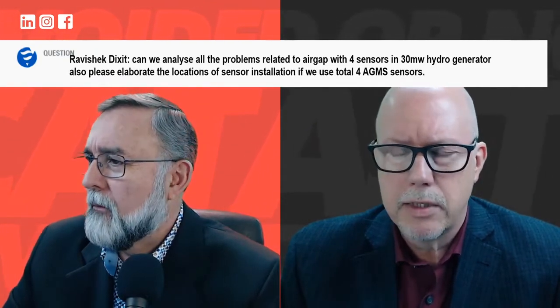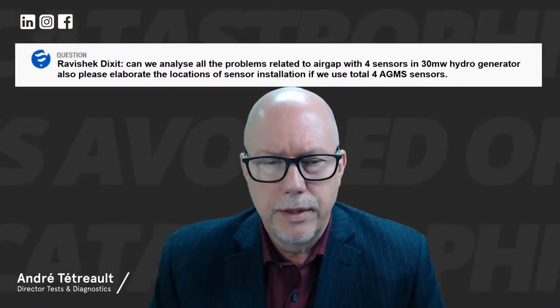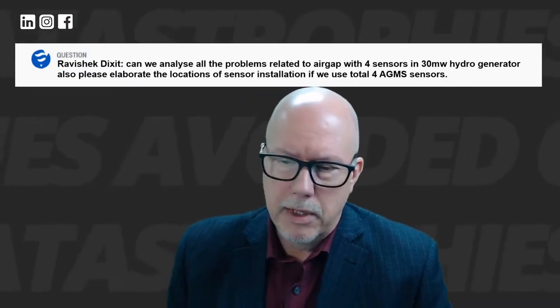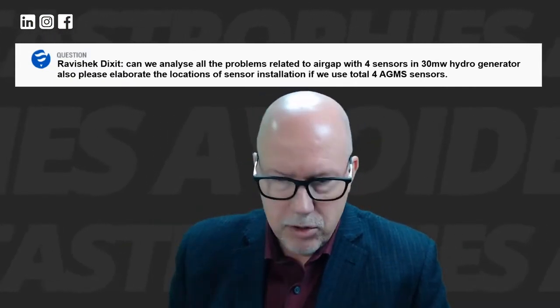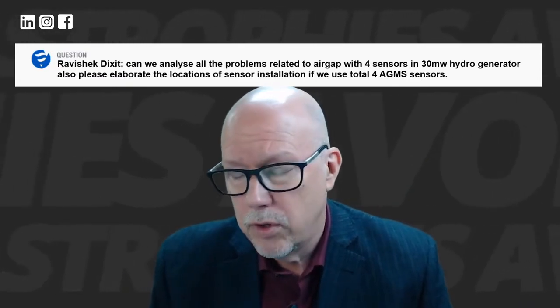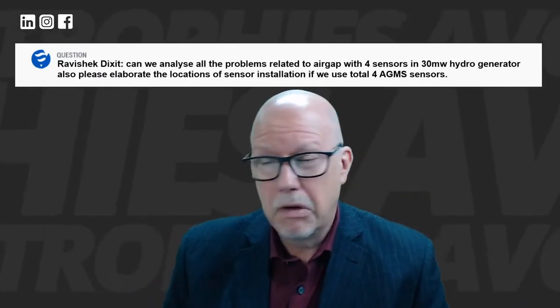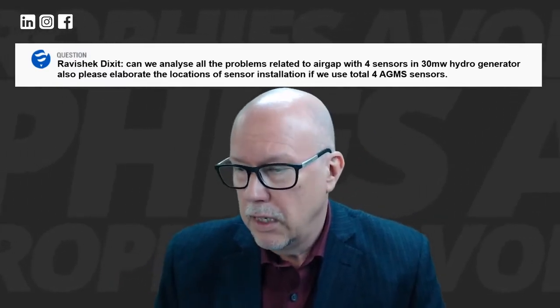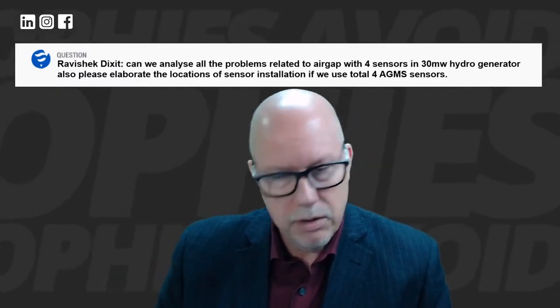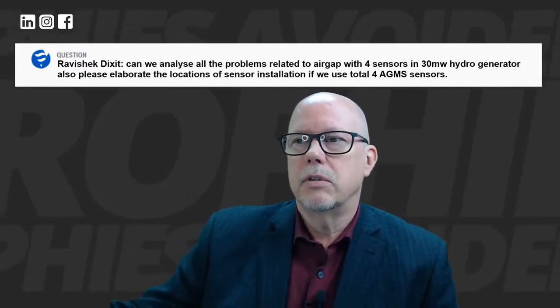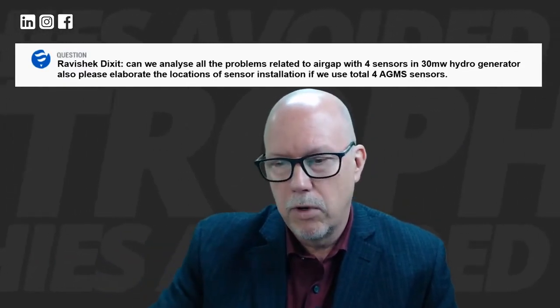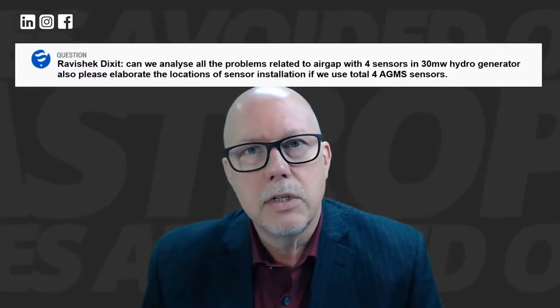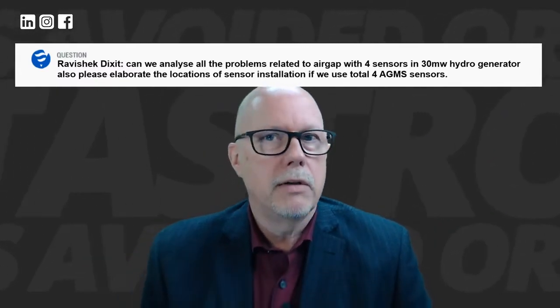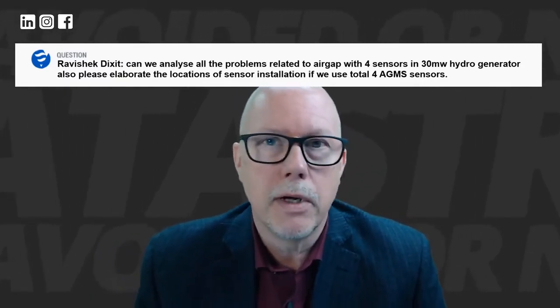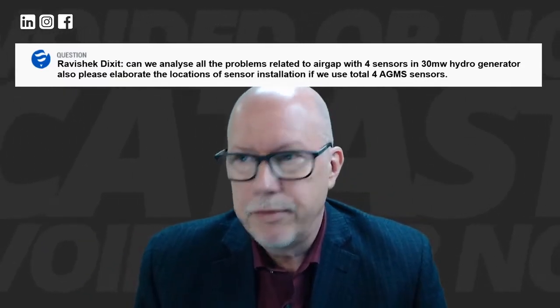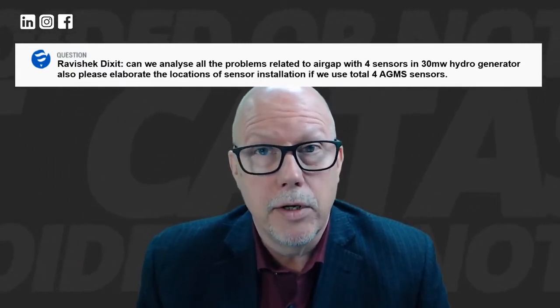I've had many discussions with utilities or OEMs talking about how many sensors, or even if sensors were pertinent, because the unit's very small, we generate only 10 megawatts, and it's not a cost-efficient exercise for us to put this type of equipment with this cost on smaller units. And my response is always, well, okay, so if this unit goes down, that's not a problem for you. If it's stopped for 6 months, that's not an issue. If it isn't, then no, you don't need any monitoring, in fact.